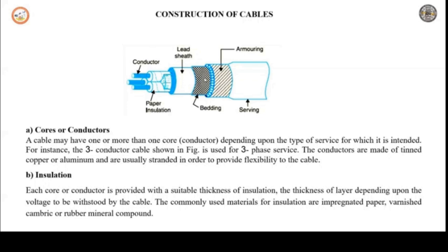Next is bedding. The metallic sheath is covered by another layer, which is called bedding. The bedding consists of paper tape compounded with a fibrous material like jute strands or hessian tape. The purpose of bedding is to protect the metallic sheath from corrosion and from mechanical injury resulting due to armoring.